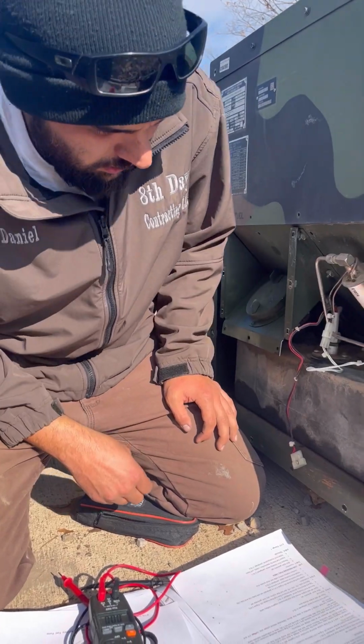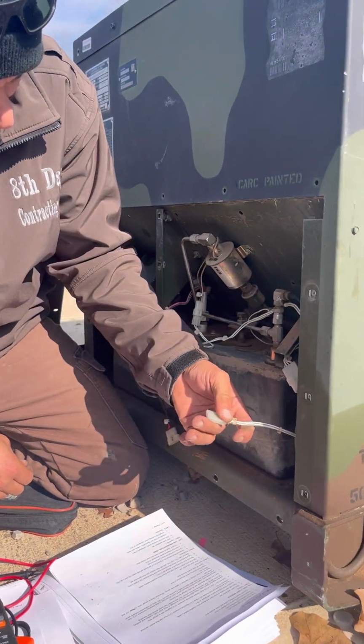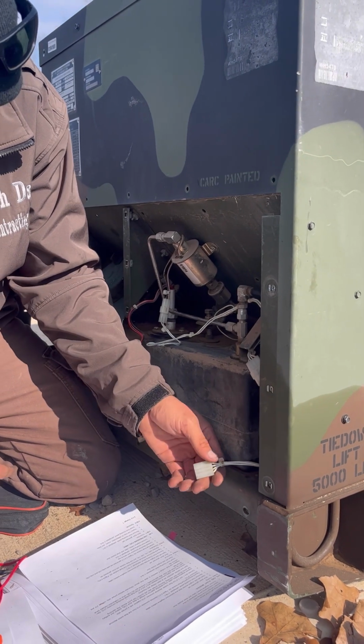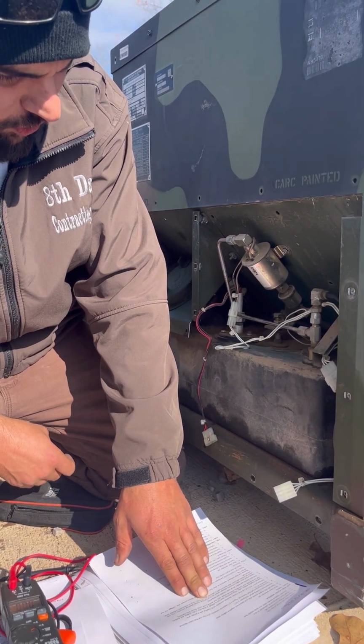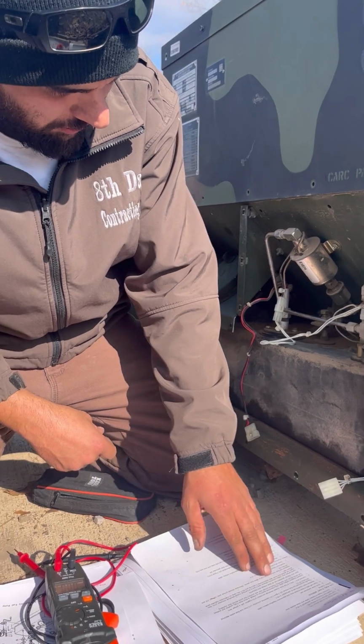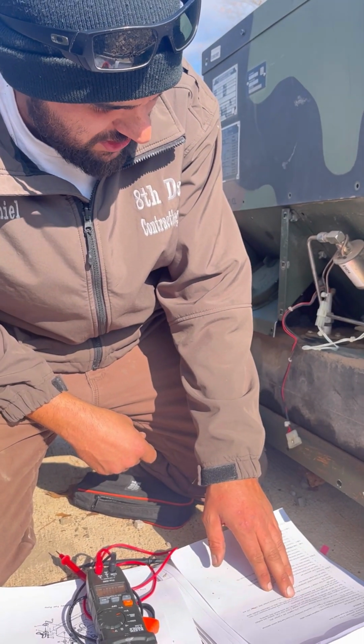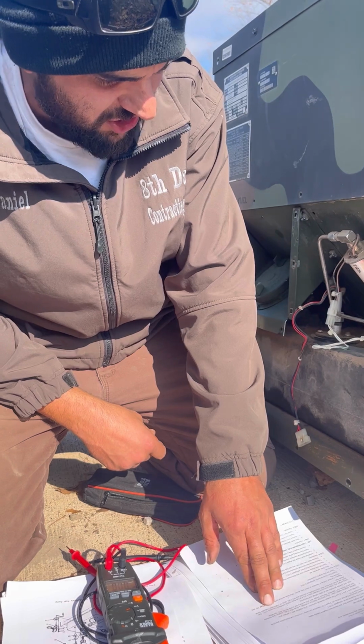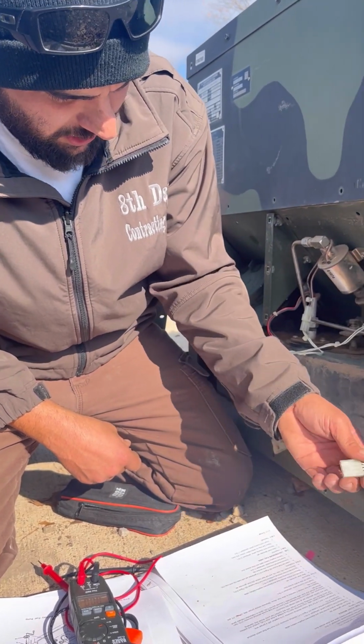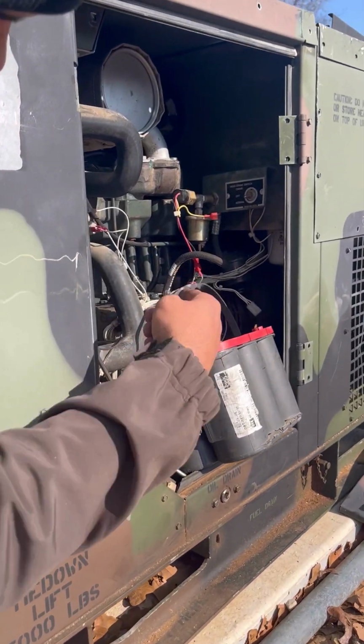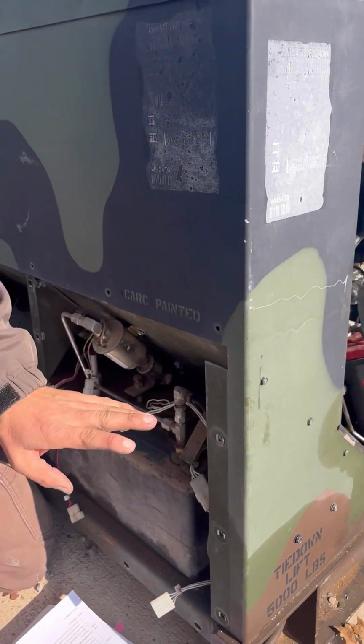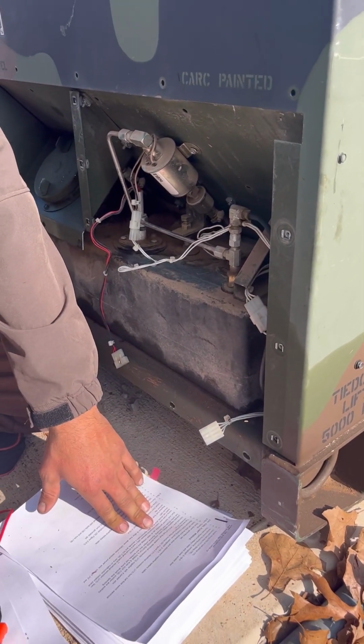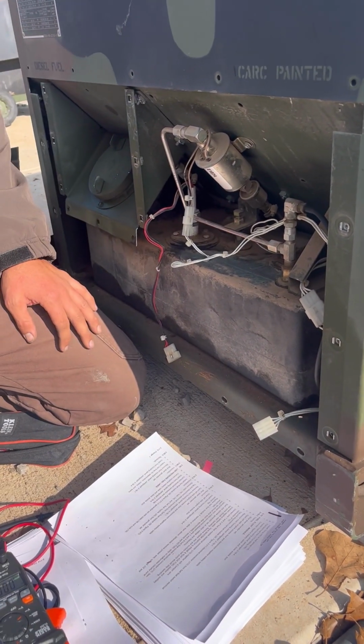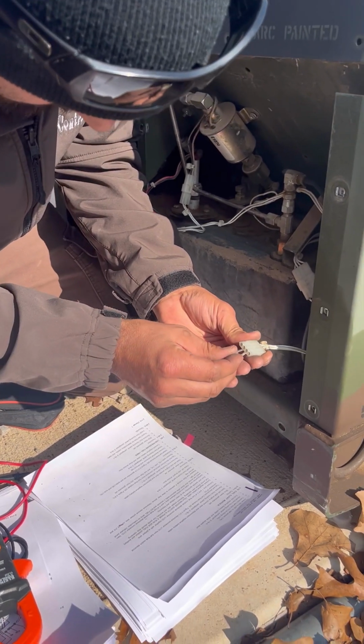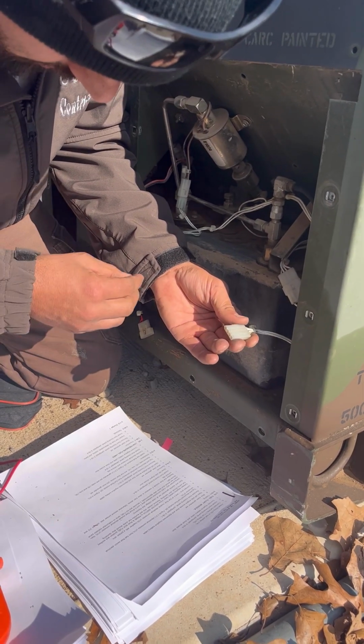Okay, so the final step in testing the fuel float module is to use a jumper wire and make a connection between pins 3 and 4 of the float module. The generator should shut down in approximately 2 seconds, and a no fuel lamp on the malfunction indicator panel should light. Our fuel solenoid shut off right there is not connected, so we're going to test and just make sure that the fuel pump kicks off, and that the fuel float module is operating correctly. So I'm going to connect these, and it said after 2 seconds the generator should shut down.